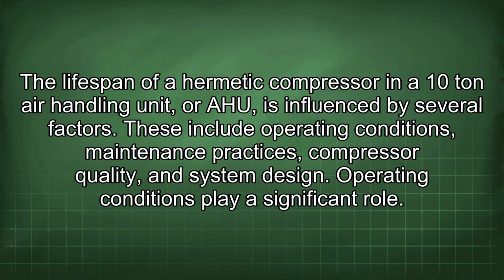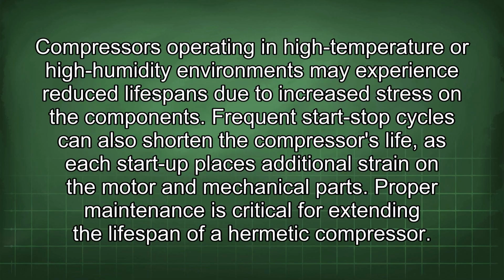The lifespan of a hermetic compressor in a 10-ton air handling unit, or AHU, is influenced by several factors. These include operating conditions, maintenance practices, compressor quality, and system design. Operating conditions play a significant role. Compressors operating in high temperature or high humidity environments may experience reduced lifespans due to increased stress in the components. Frequent start-stop cycles can also shorten the compressor's life, as each start-up places additional strain on the motor and mechanical parts.